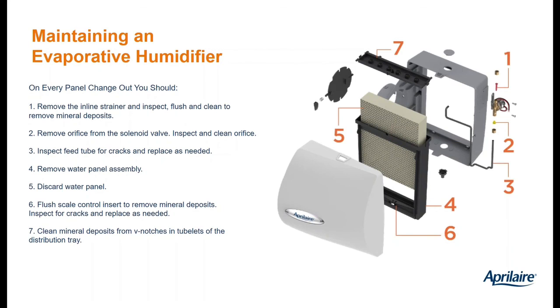If you're not having a problem, the maintenance I would do is follow the water flow path. Take the scale control insert and the distribution tray out. Make sure that you don't see any accumulated mineral deposits that are plugging it up. Make sure nothing's cracked. Take the water panel out, throw it away, put a new one in. Make sure the drain is open. The drain line has a continuous downward slope and it's not getting microbial growth in it. And you should be good to go for the next season.